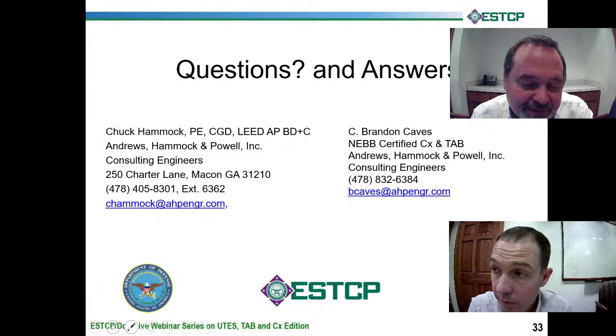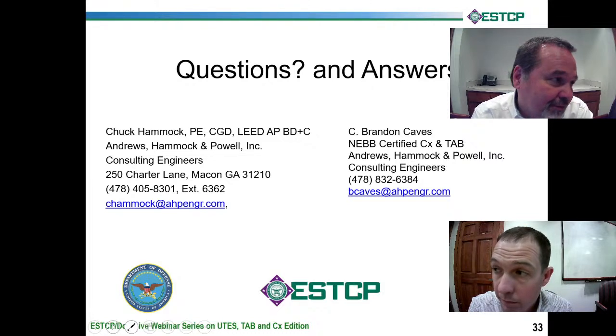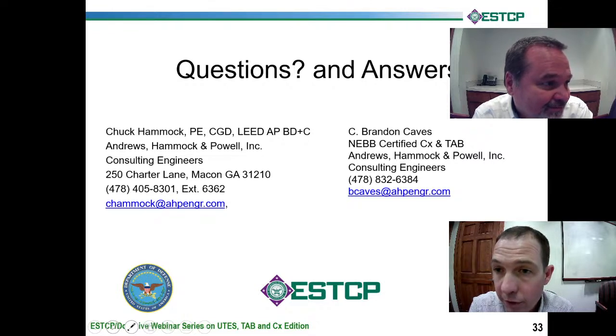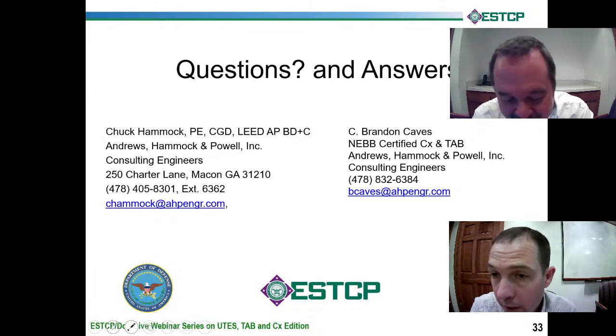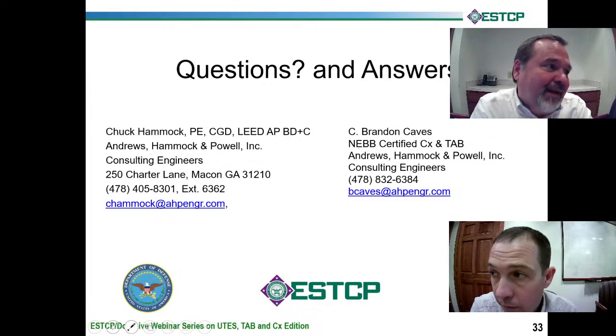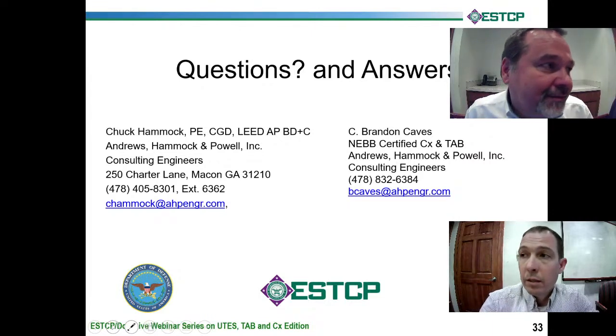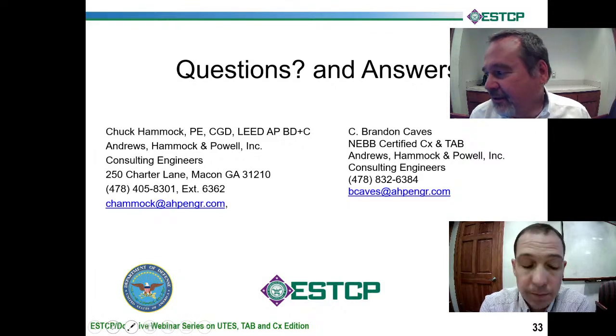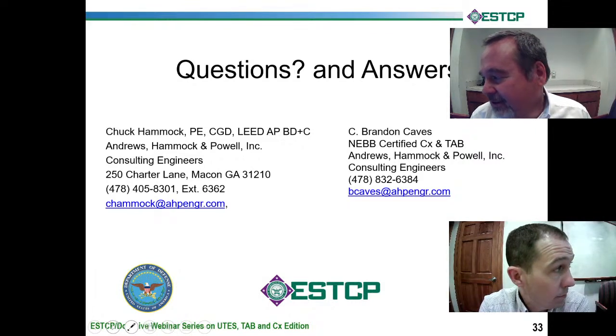As Brandon says, if there is a modulating valve there, possibly on the chilled water side or the hot water side, and that's a smart valve that's communicating its position back to the central controller, and it says, "Hey, I'm half open or I'm two-thirds open," you've got to have that piece of information. Well, you don't. It doesn't necessarily have to send the signal back, but if you know you're sending a 100% signal, you're just assuming it's 100% open. Yeah, right. It's not necessarily direct feedback, but whatever position you've told that valve to go to. And so that's right. All right, so let me hit the next one.